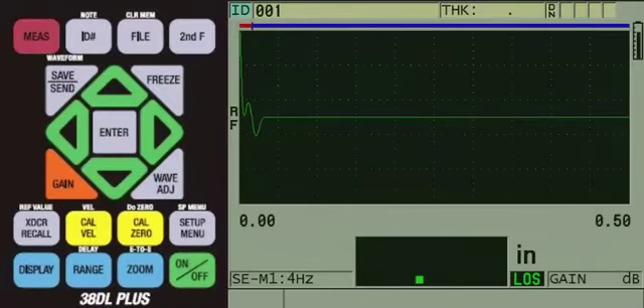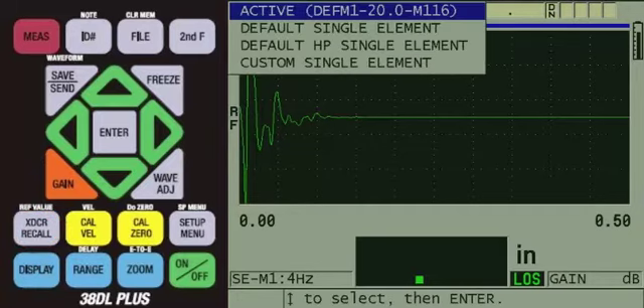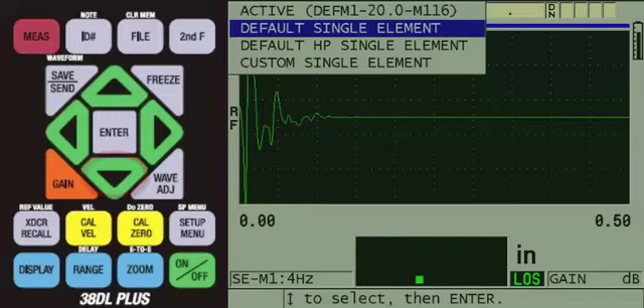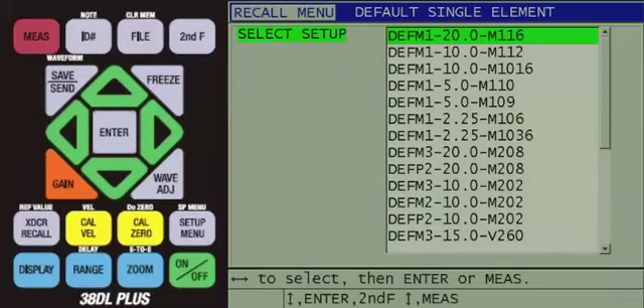The first step would be to connect the transducer and plug the transducer cable into the TR1 at the top of the instrument. Then turn the instrument on. Once the instrument is on, press the XDCR recall key. Since we are using a 2.25 MHz transducer, we will press the down arrow to default single element and then press Enter. Here you will see the list of default single element transducer setups.